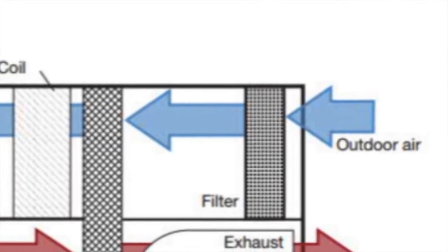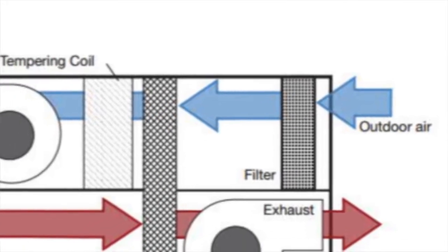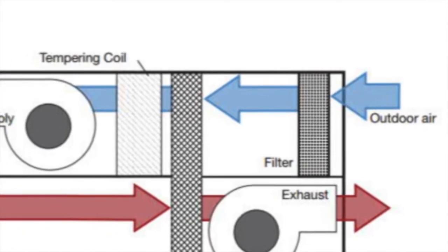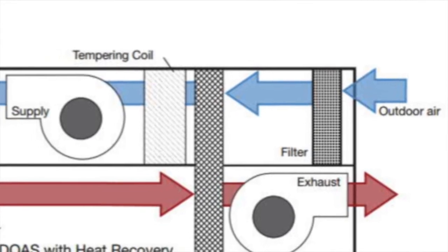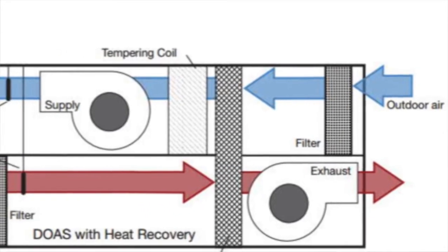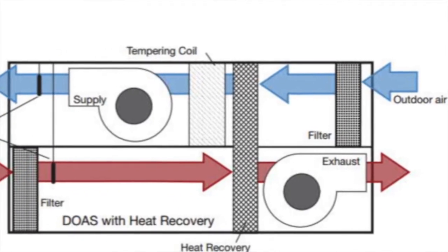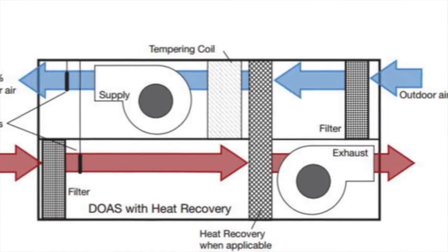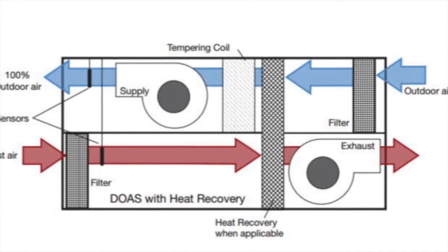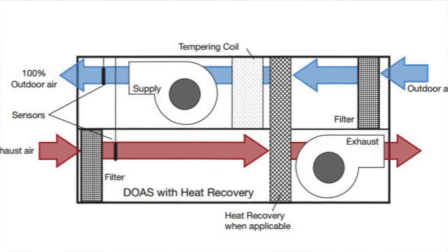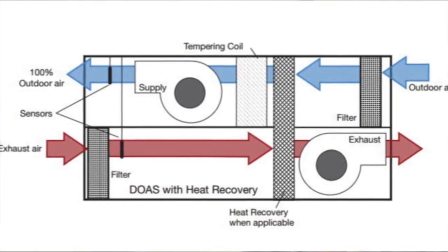The system works by first bringing in fresh outside air, filtering it, and running it through an energy recovery ventilator. Once some of the heat energy is transferred to it from the exhaust air as it exits, the warmer incoming air is run through a tempering coil to precondition it further. The coil is fed with hot water that is heated by the building's thermal storage system. There's also a direct expansion cooling coil to handle the small cooling load on the building if necessary.